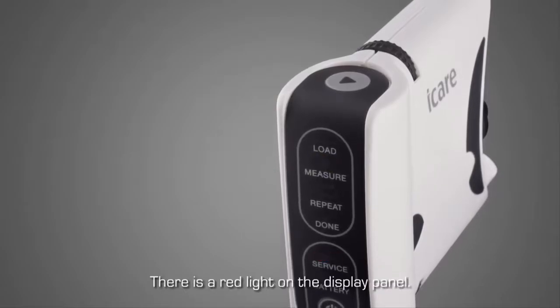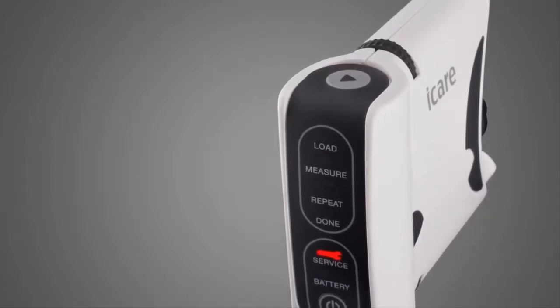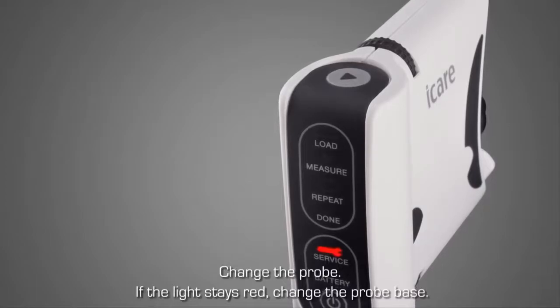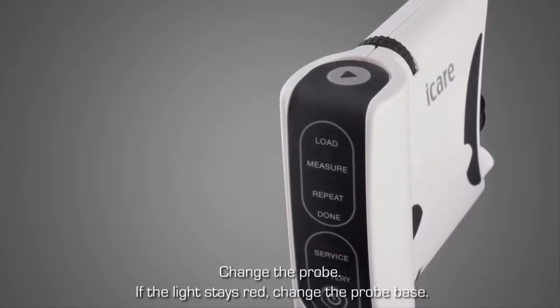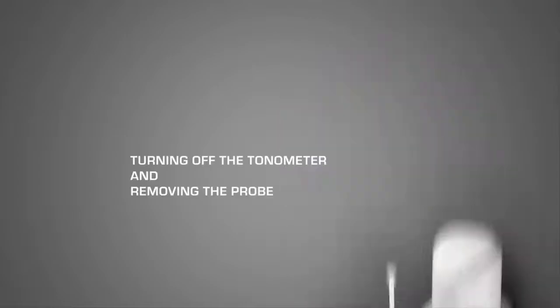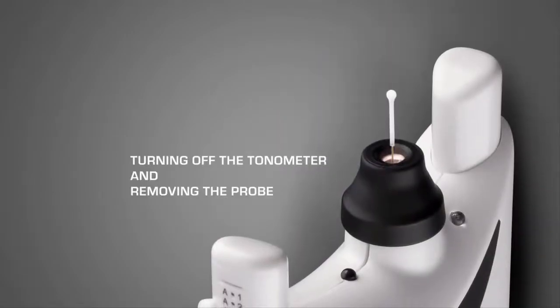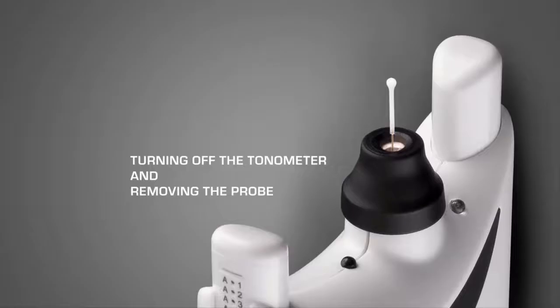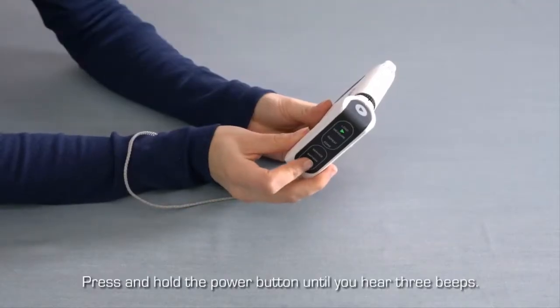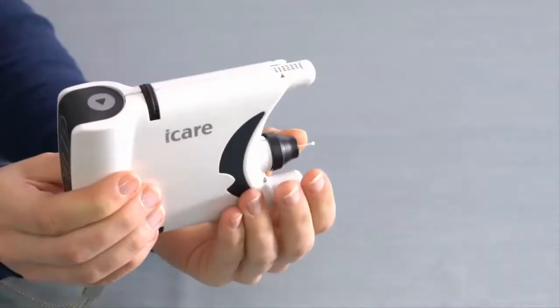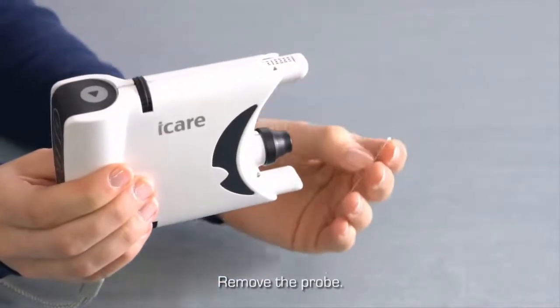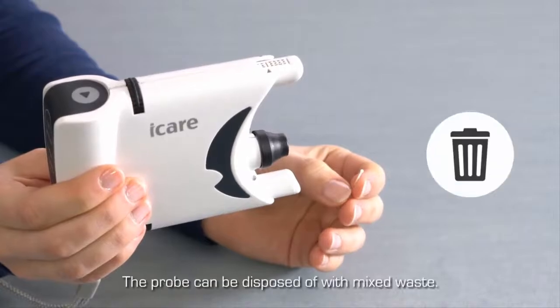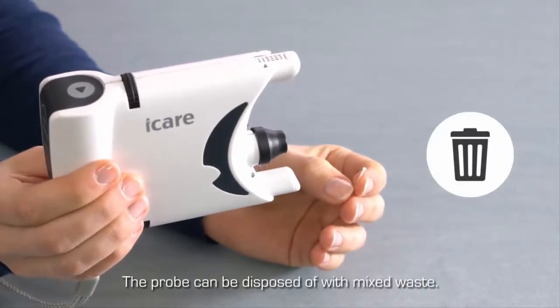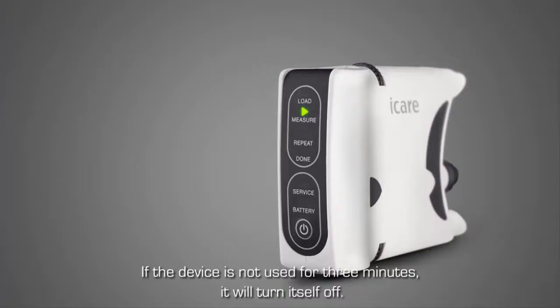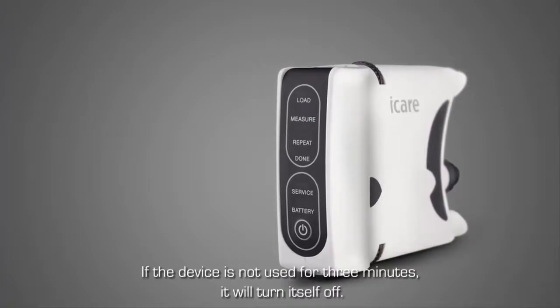There is a red indicator light in the display panel. Replace the probe. If the light is still red, change the probe base. Start the measurement again. Turning off the tonometer and removing the probe. Press and hold down the power button until you hear 3 beeps. Remove the probe by pulling it out of the probe base. The probe can be disposed of with mixed waste. The tonometer will turn itself off if not used for more than 3 minutes.